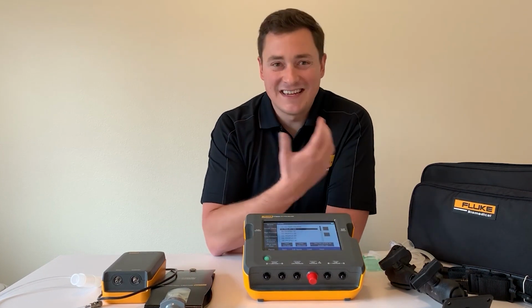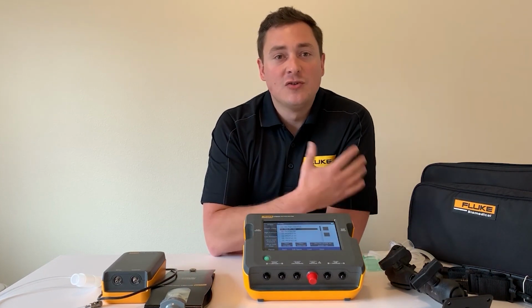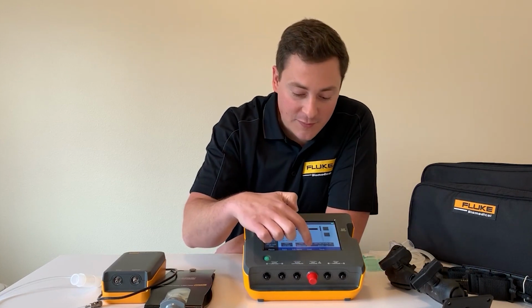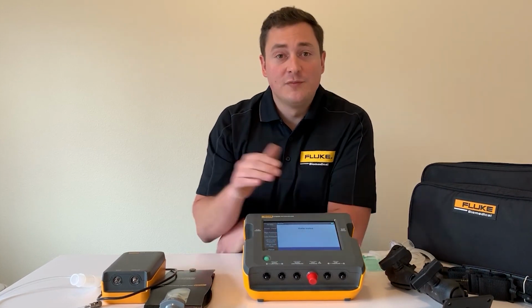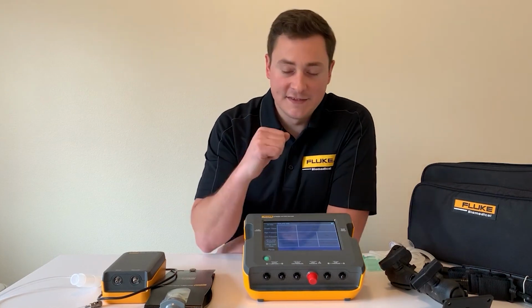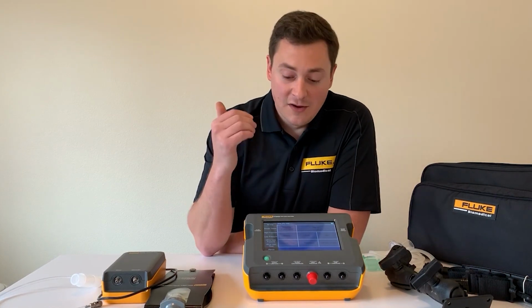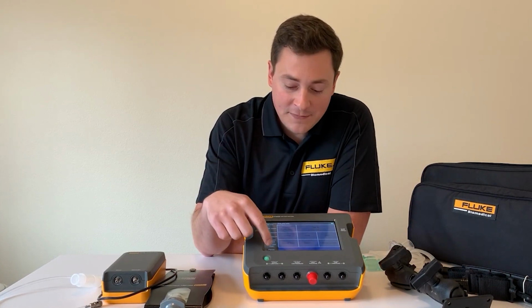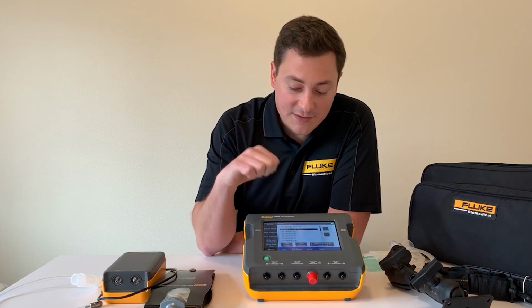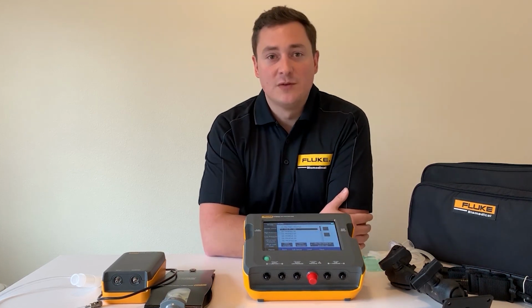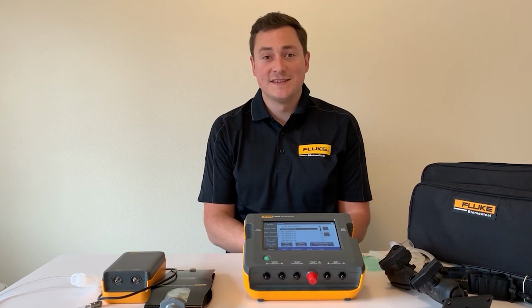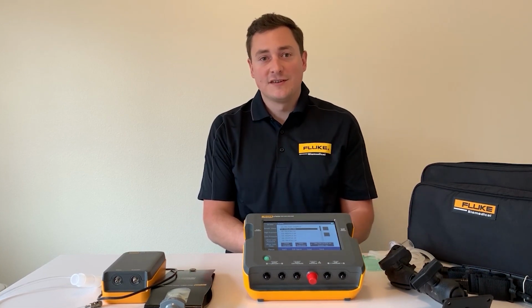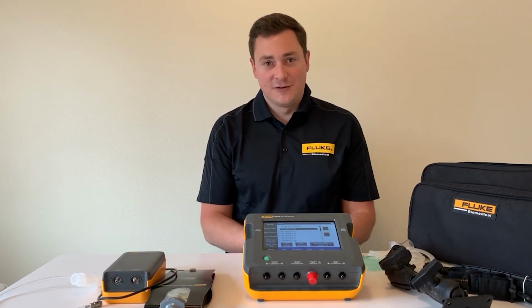So again, all that setup you have to do between brand and model, you don't have to do anymore, because all you have to do is show up and press load. Press load, make your connections, you're ready to go test. This saves you time every single day. The other option on test profiles is that you can load it at startup. So if you're testing one brand and model consistently, you can have that load right at startup and make it even faster for you.